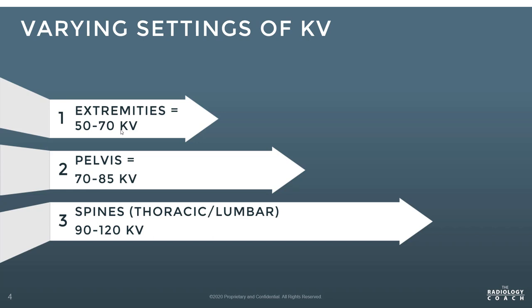I tend to err toward the 65–70 KV range. Historically we used lower KV around 50 to get higher contrast — more black and white so you can see the bones more clearly. But with today's digital systems, the algorithms automatically produce an image that looks appropriate. The contrast looks good and the doctor sees what they need. More importantly, a higher KV setting provides lower doses to patients.